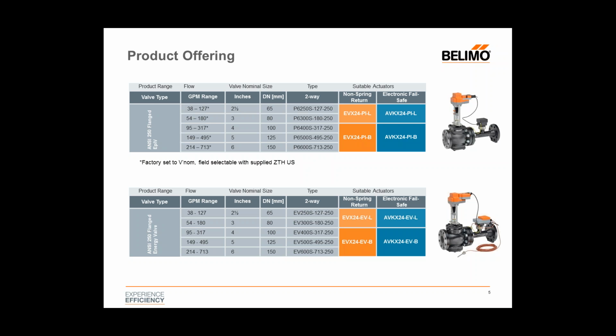The energy valve down below is very similar. So it's 38 to 127 for the 2.5 inch, and then 214 to 713 for the 6 inch. And you can see the corresponding flows there. All of these flows are available in our product flyer and, of course, our PGPL. Again, available in non-spring return and electronic fail-safe.